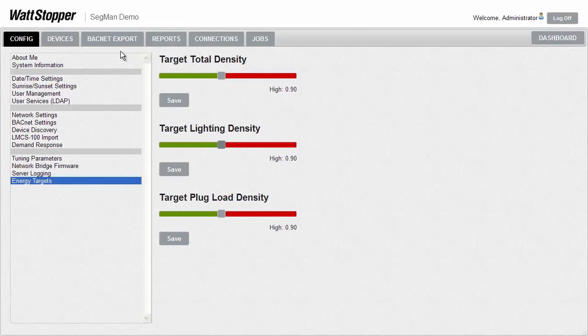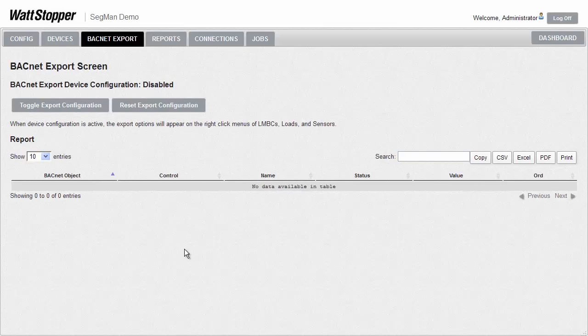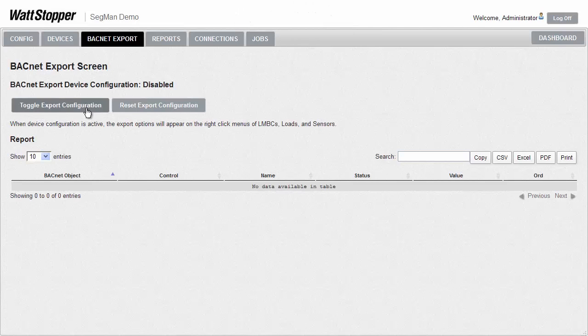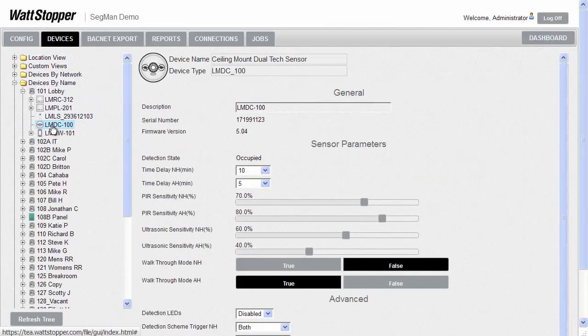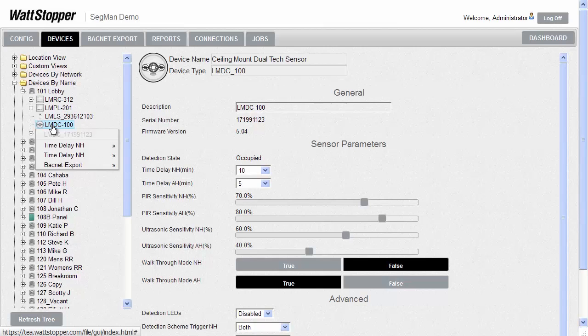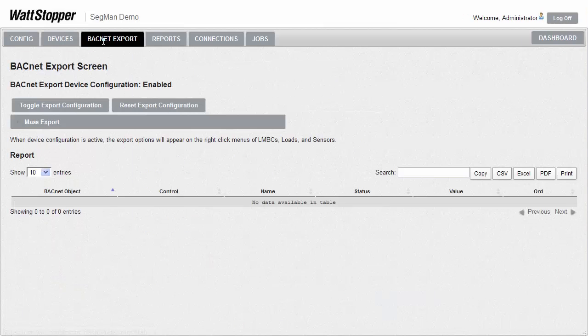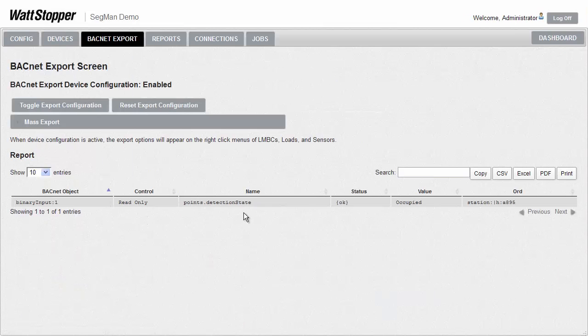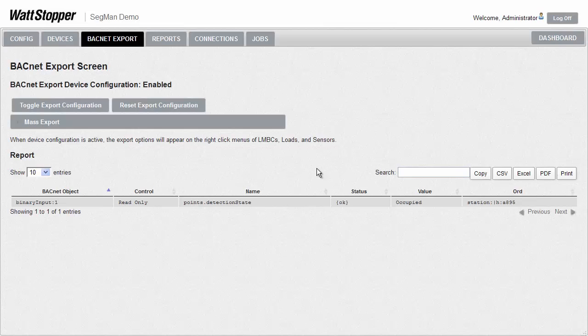Next, we've got the BACnet export tab. This export table lists all the BACnet parameters that we've chosen to make available to any integrator on the job. To create or add to the list, somebody would start by going in and clicking the toggle export configuration. When I do this, you'll notice there's a quick message up here saying it's been toggled on and I am now able to add new objects to the list. I can now go to any device on the device tree. Let's choose that same occupancy sensor. What I want to do is set up the system to share information from just this occupancy sensor, just its detection state as a BACnet point. Once we've done this, we can go back to the export table and see we've got a listing of all the BACnet objects that the integrator who's communicating to the segment manager on the job will get when they pull data from the segment manager. One reason this is so helpful is because the export table sets up a firewall between the integrator and the DLM system.